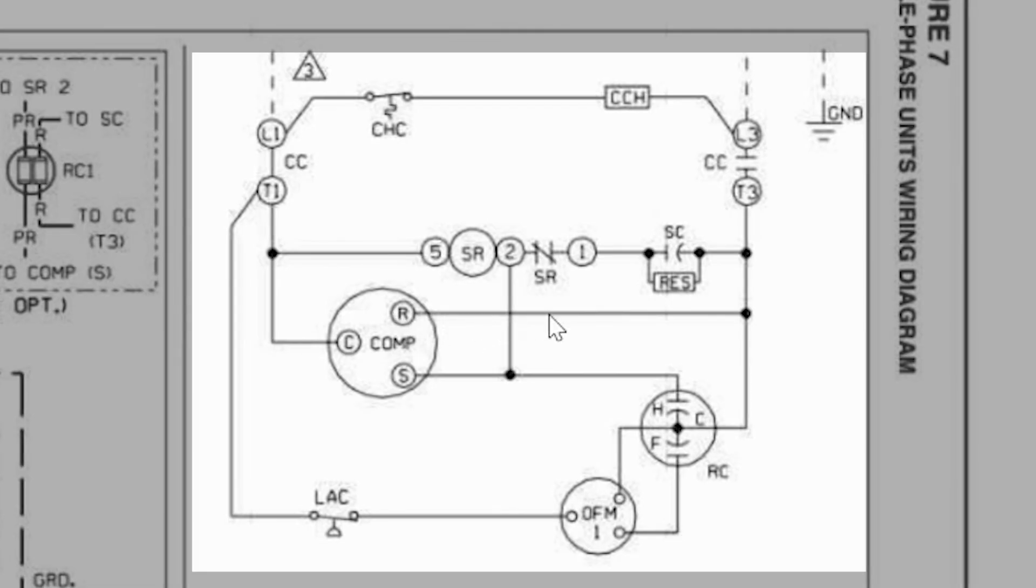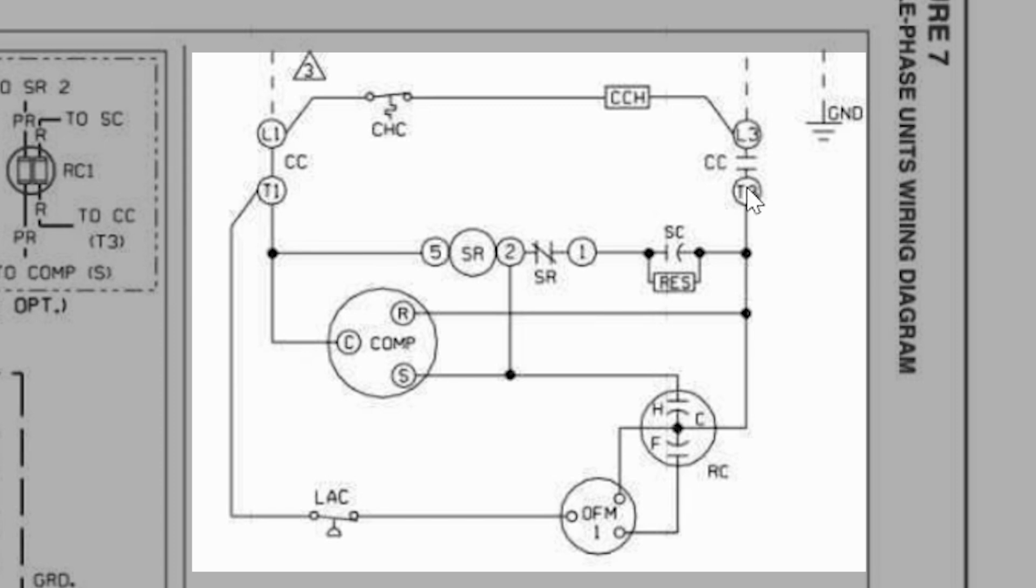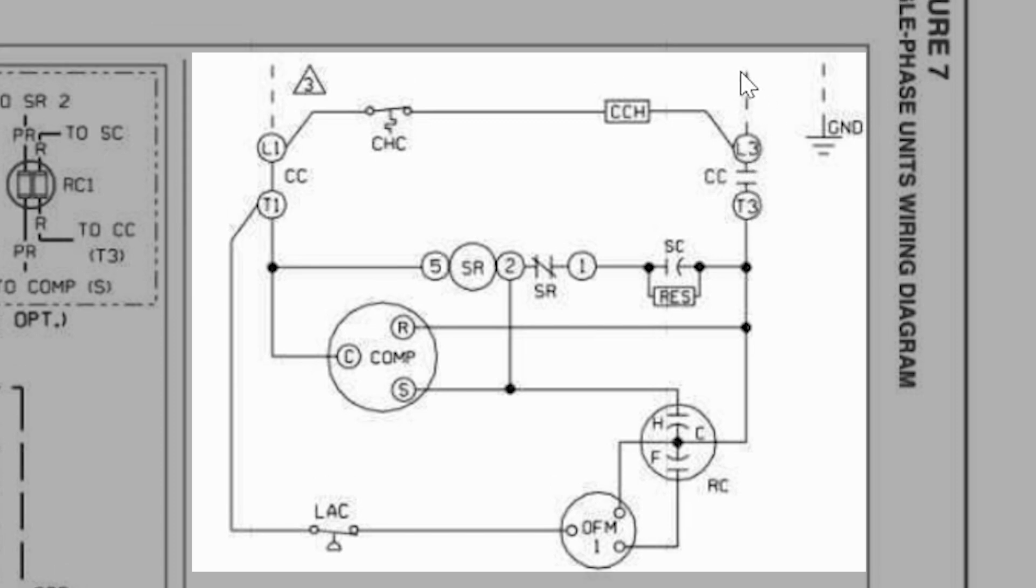Our R is going to go to the other side of the circuit. This is what we call the run side. And in this case, the side that has the contact that opens and closes, that's what we're going to call the run side. It's fed by one leg of power coming from the utility, one leg of 120 volts. Then that feeds through and goes to the run side.